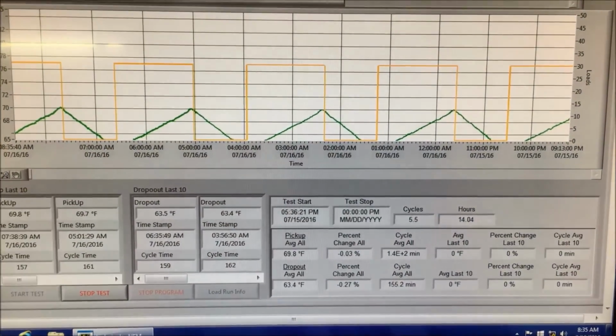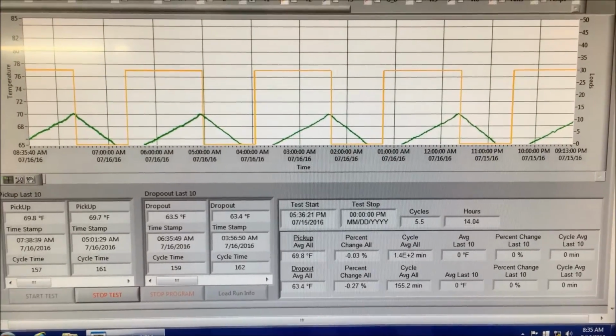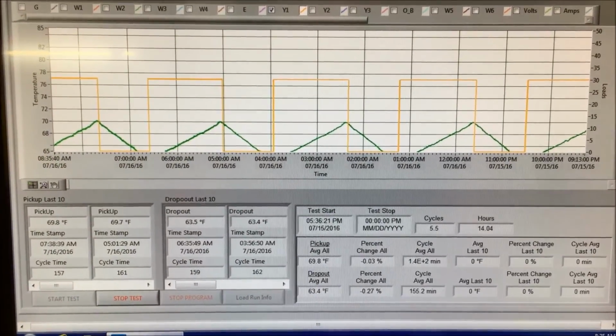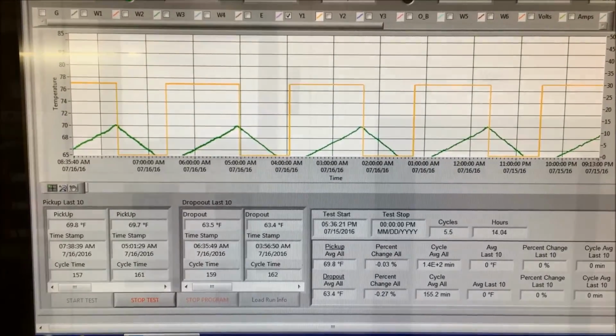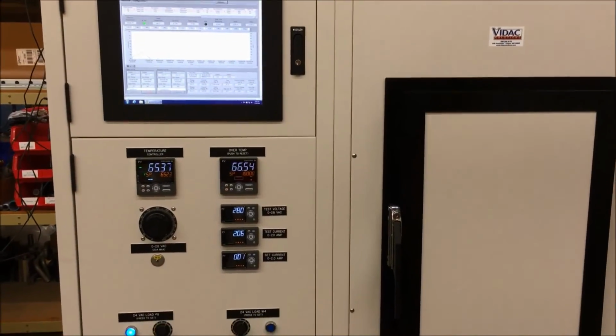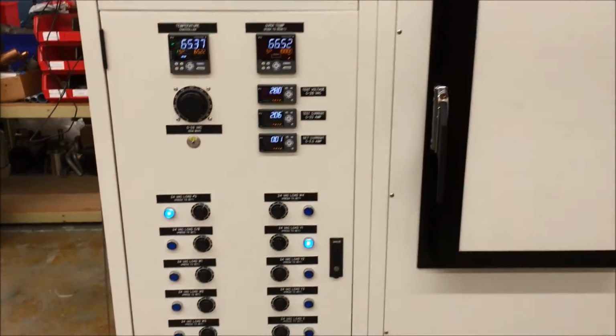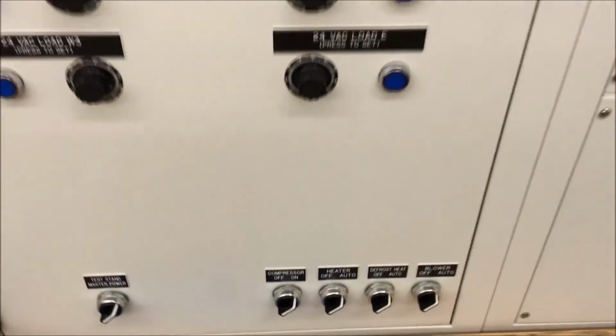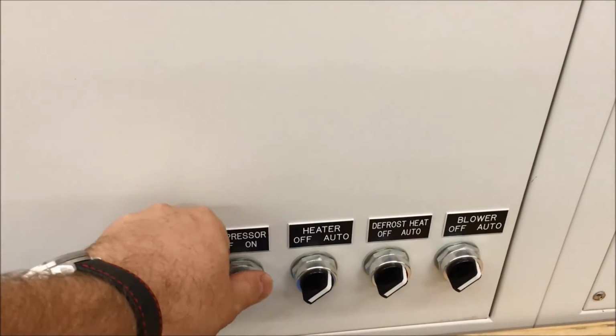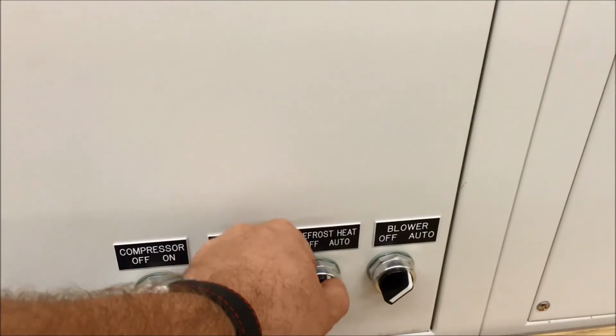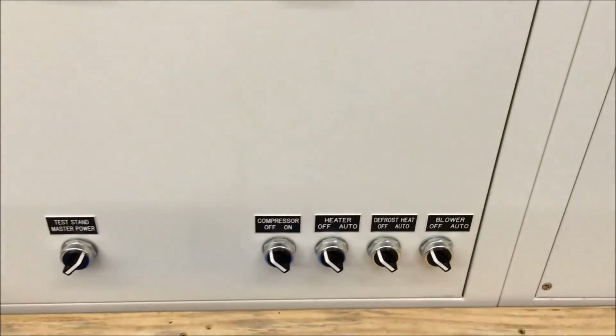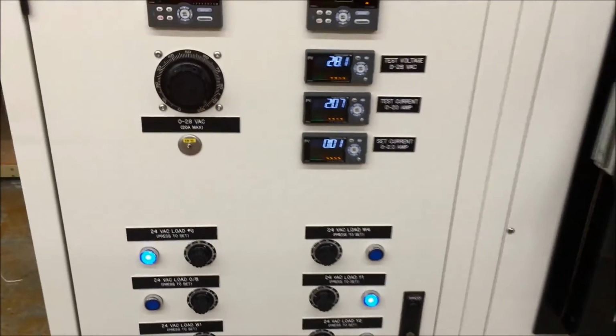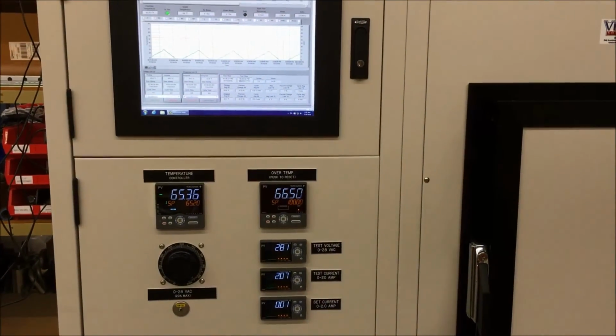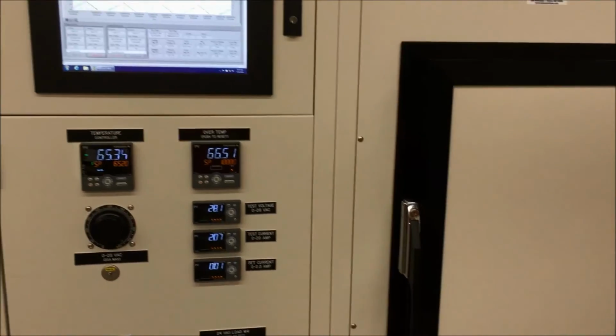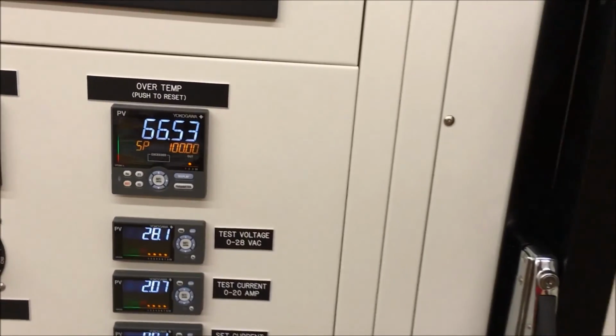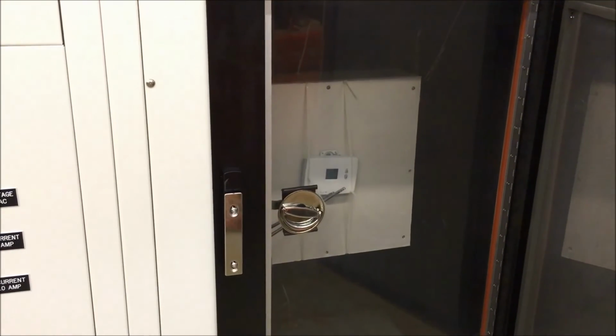And you can see how smooth the temperature transitions are. There's really not much overshoot. Really tight temperature control. And once our test is completed, we just simply turn off the box and remove the thermostat. The easiest way to do that is to turn the compressor off, heaters, and blowers. Now the box is sitting here in a live state, but it's not consuming very much energy at this point. You can remove the thermostat and prepare for the next test.